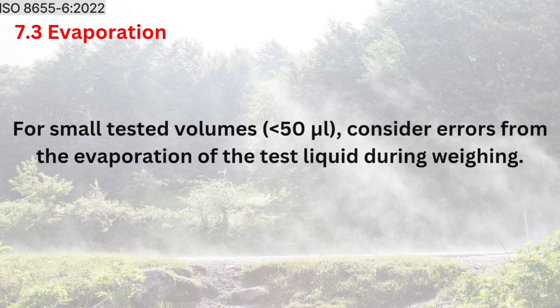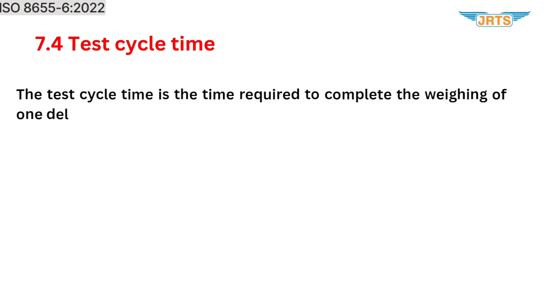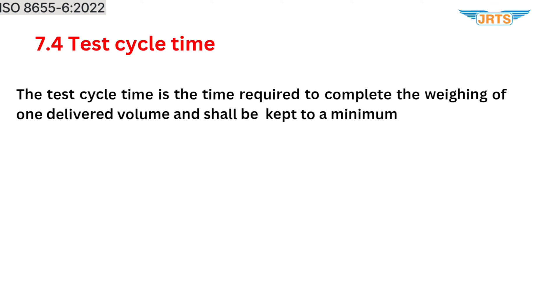Section 7.3, Evaporation: For small tested volumes, consider errors from the evaporation of the test liquid during weighing. Section 7.4, Test Cycle Time: The test cycle time is the time required to complete the weighing of one delivered volume and shall be kept to a minimum.